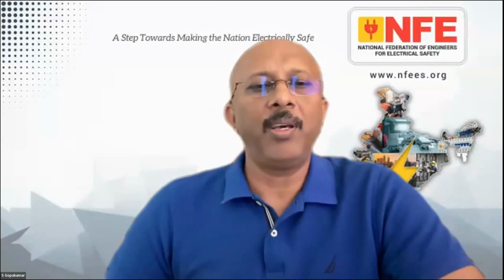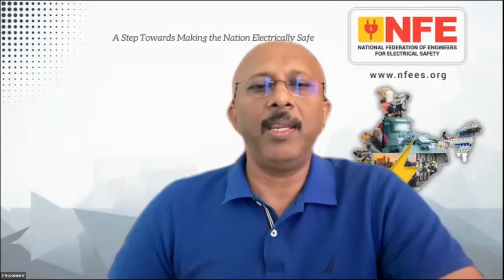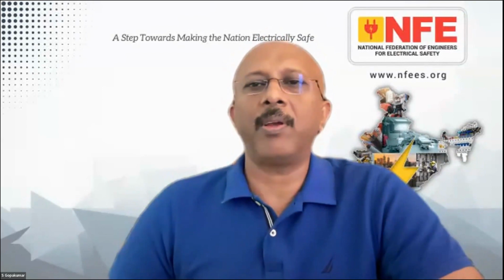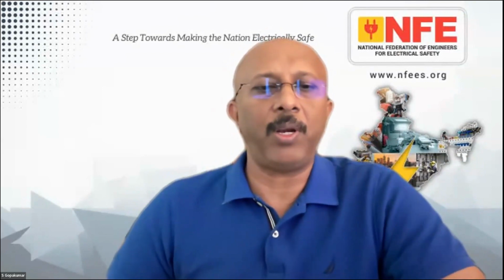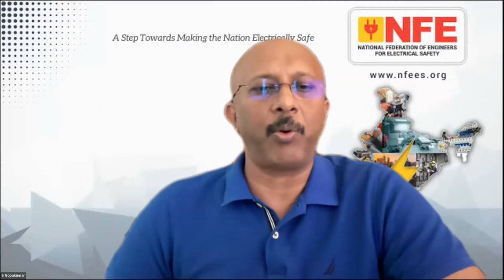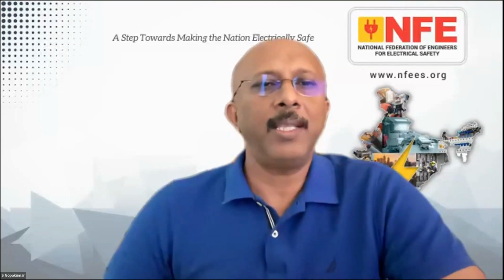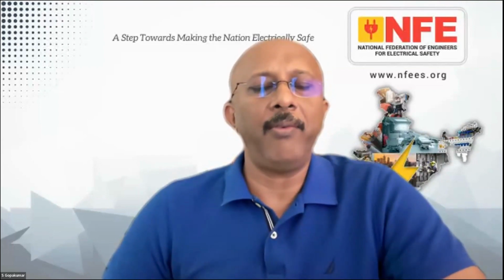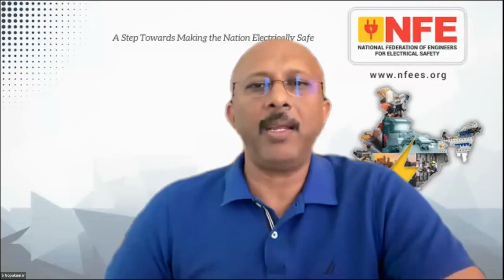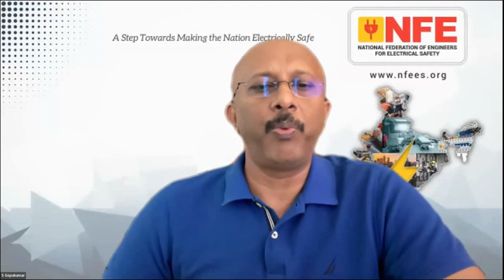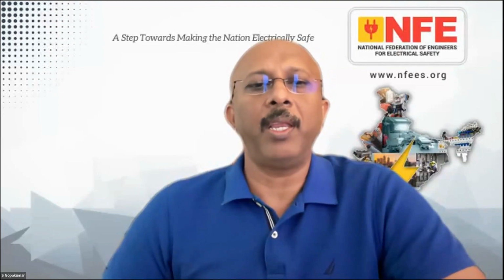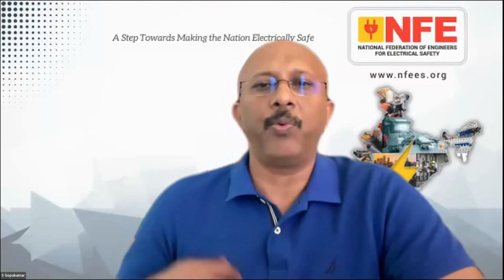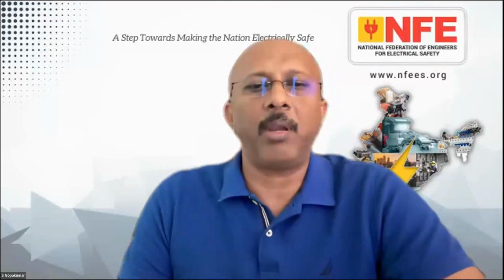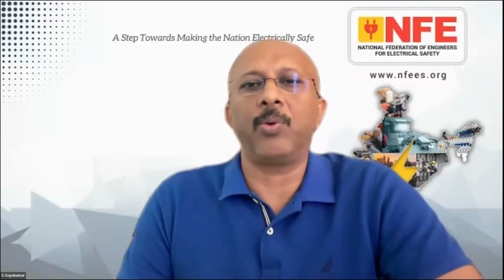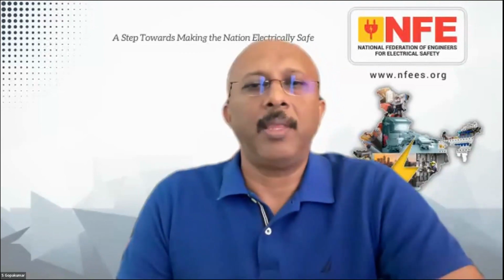So this is not matched. In the Indian context, to reduce it, first we should check whether the rating of the protective device is proper. Are the live conductors, the current carrying conductors, properly rated? Then we have to check whether the return path of the fault loop has any loose contacts and so on. So in the Indian context, we have to do a thorough check of the entire circuit. That would be better. Thank you for that.